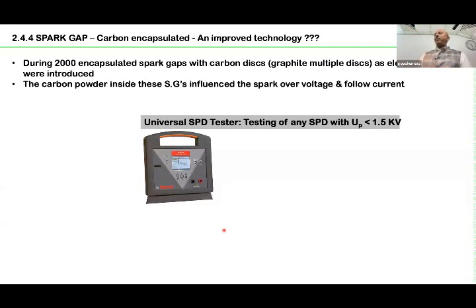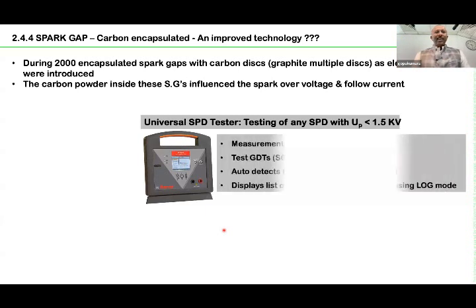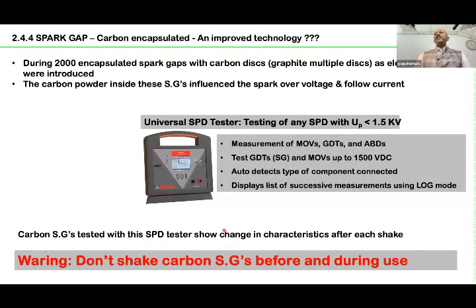It's a sealed SPD. The problem of this SPD is that the graphite will have fine powder. If you shake the SPD very well and then test the SPD, it will show one characteristic: voltage protection level maybe 1.2 kV. Then you shake it again 2-3 times and test it, it shows another characteristic. The voltage protection level will change. So as a joke, I used to tell that, like in the medical store, once we buy some medicine, it says shake well before use. Like this, don't shake this device while using, you will be in trouble.